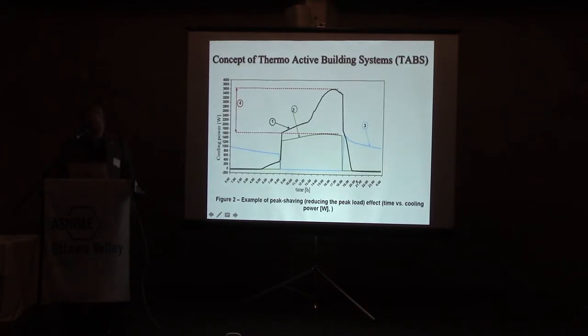So the idea is, when you look at this graphic here, that's 24 hours in an office. People come in the morning, then turn on lights, and then the load gets higher and higher because of sunshine, and then you have a peak here for your cooling system. I'm mainly talking about the cooling. So when you design your full air system, you would normally design it for the peak load you have. Then people are leaving and there's no sunshine anymore, the load goes down.